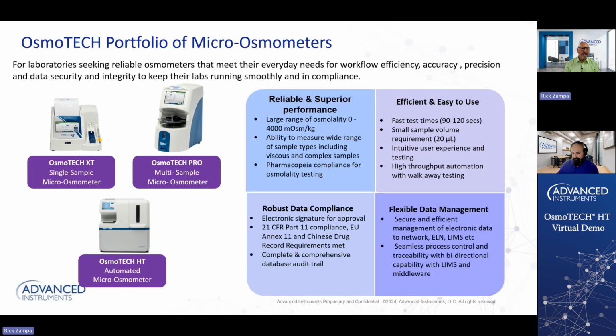They have flexible data management capabilities, the ability to connect either through a LAN network, ELN, or LIMS system, which allows you to control your data and manage your data off the instrument once you've gotten your test results. Robust data compliance, with electronic signatures for approvals, so you can comply with 21 CFR Part 11 of the FDA or EU Annex 11, and the Chinese drug record requirements can be met with these electronic signatures. We also have a complete and comprehensive audit trail that will give you everything you need to know about the instrument and allows you to go back and check if any changes were made on that instrument.